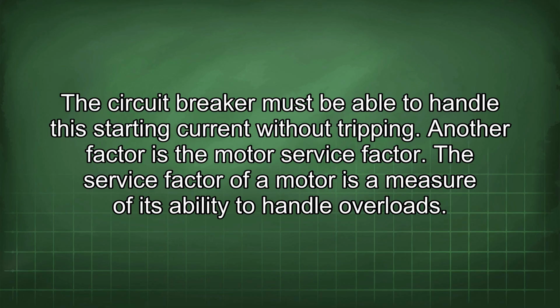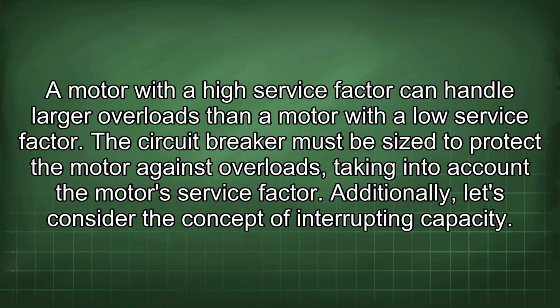Another factor is the motor service factor. The service factor of a motor is a measure of its ability to handle overloads. A motor with a high service factor can handle larger overloads than a motor with a low service factor. The circuit breaker must be sized to protect the motor against overloads, taking into account the motor's service factor.